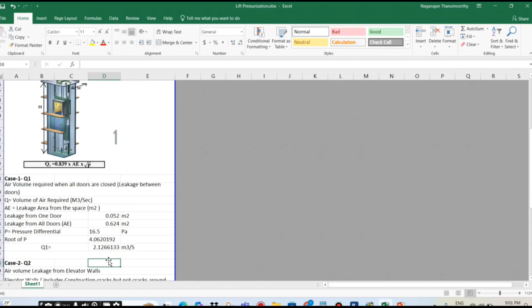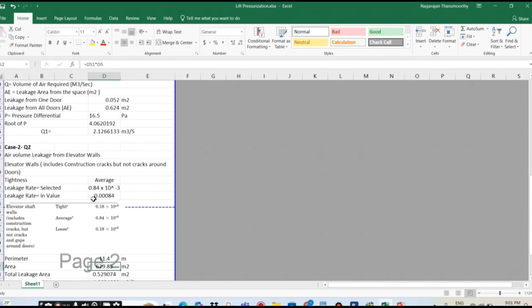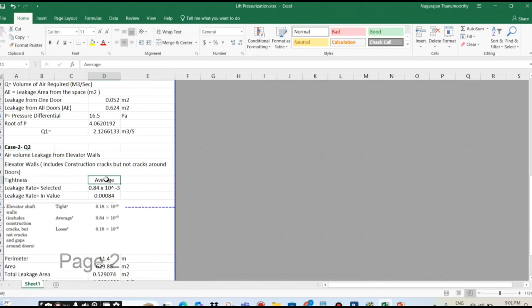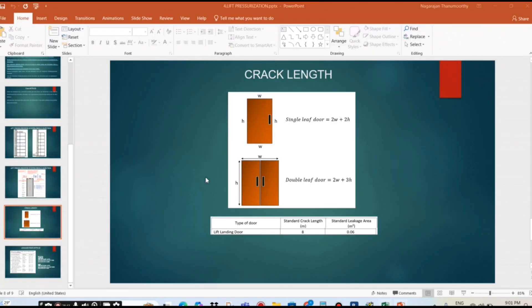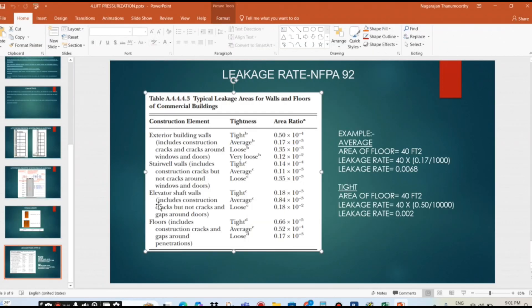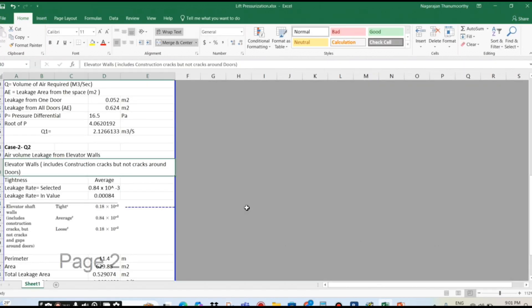Air volume leakage from elevator walls. So this one — yesterday I told you about the elevator wall. If you see this one, we have given elevator shaft walls: tight, average, loose. So yesterday also we told you, not only for elevator — staircase also we have the same issue — it's a fire-rated arrangement. So normally mostly people don't consider that one. It's up to your local code and your local civil defense. If they tell you to consider, yes of course we have to consider, otherwise we don't need to worry about that one. We can avoid that one and only consider the leakage rate.